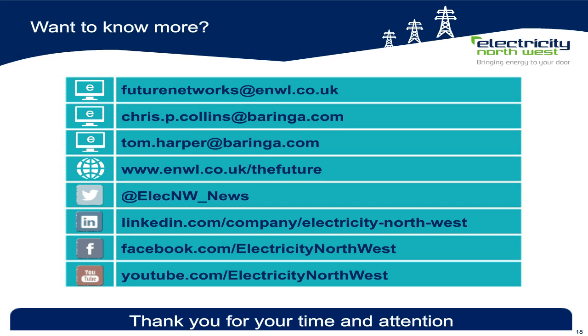There are a few questions here that relate to, well, actually, if I just summarise, there's one that says, how do you manage the undervoltage problem which naturally coincides with peak demand? And there's a query around whether CLASS works for constant power load. I think these are dealt with by the same answer, which is that the purpose of CLASS is to monitor each primary substation in real time, effectively, and determine what response can be achieved from that particular substation, from that particular transformer, and aggregate up as required to deliver the service. So if indeed there are loads that don't show the relationship between voltage and demand, that will be monitored as part of the system, so that won't be a surprise. That's precisely what the system should be doing.